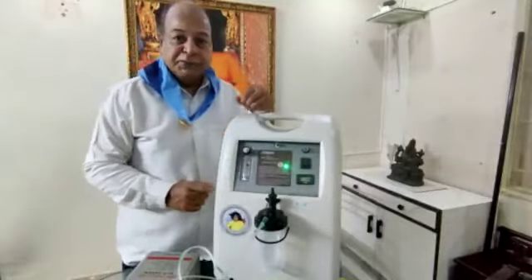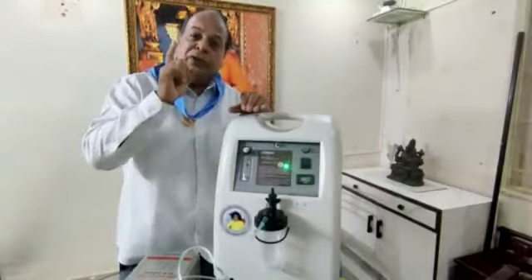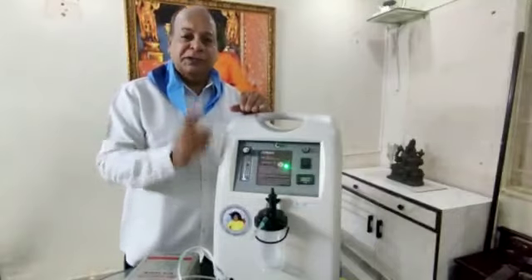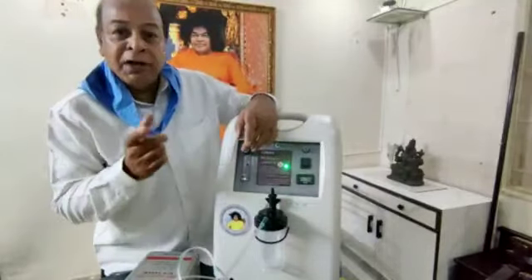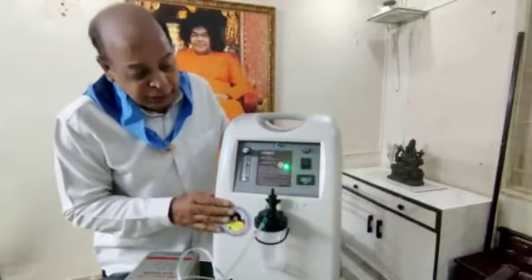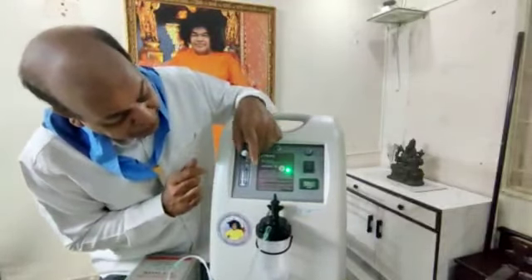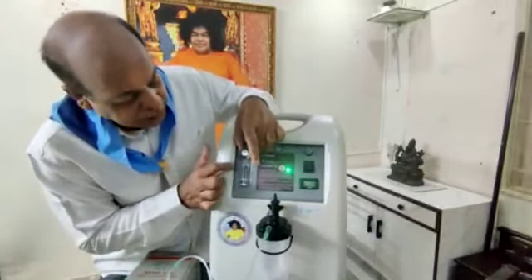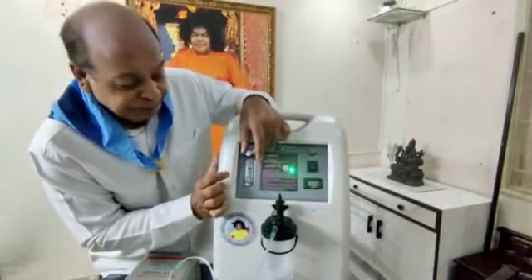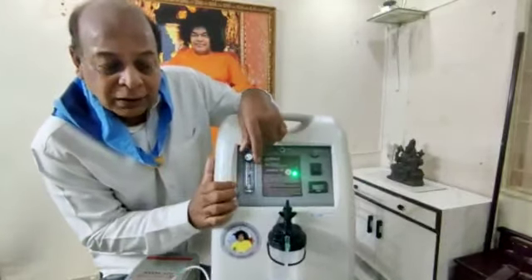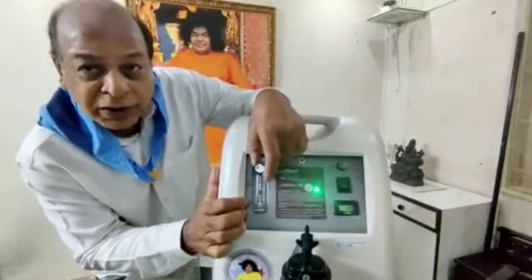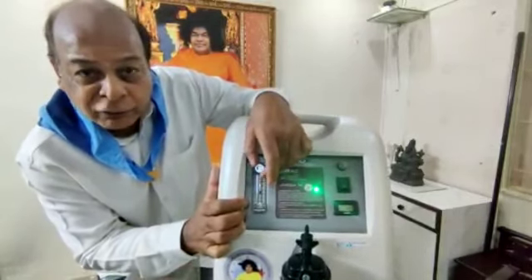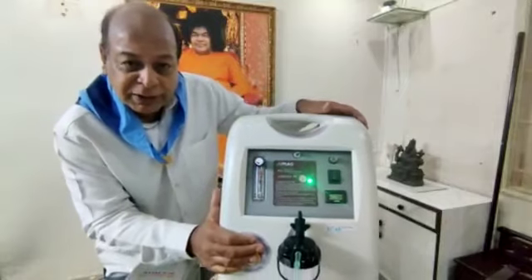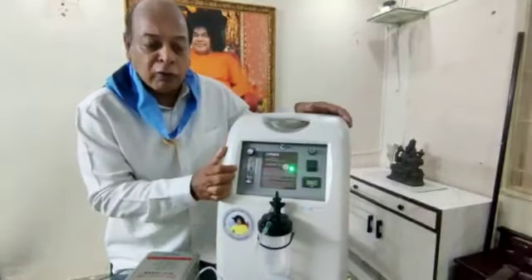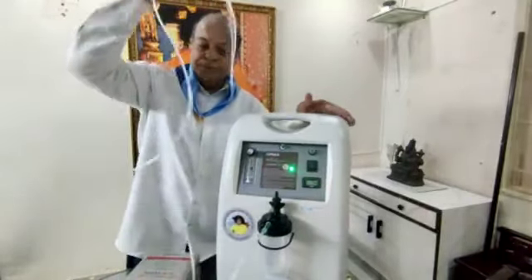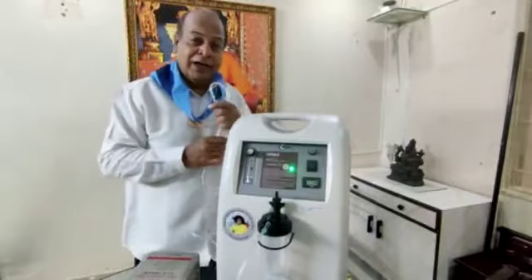This oxygen concentrator should be used only on the doctor's prescription. He will let you know how many liters should be taken. If you look here, if you turn this, the ball rolls up and down. So you can set it at 2 liters per minute, 3 liters per minute, 4 liters per minute. The doctor's advice will be there, and based on that you can set the outflow of the oxygen into the cannula. Now some very important guidelines.